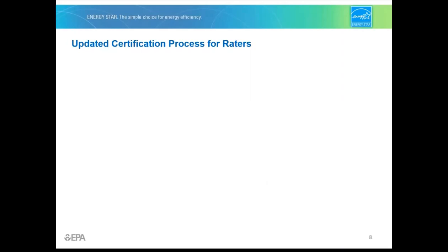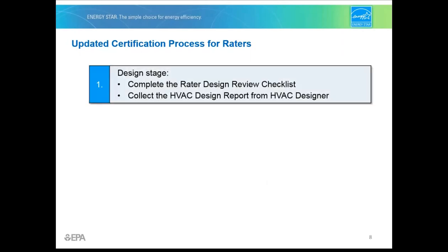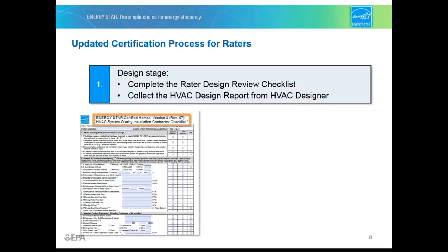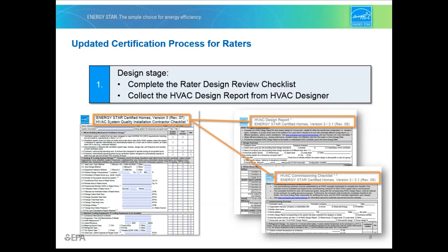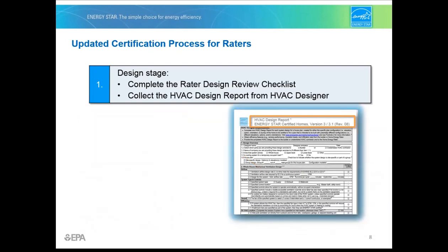Let's move on to the updated process for certifying a home and the role you'll play. At the design stage, you'll complete the rater design review checklist. Among other tasks, you'll review the HVAC design. With Revision 8, the HVAC system QI contractor checklist has also been split into two documents: the HVAC design report and the HVAC commissioning checklist. To review the HVAC design, you'll need to collect the HVAC design report — but this is the only design document you'll typically need. You'll no longer have to collect the full load calculations, the AHRI certificate, or separate documents for the ventilation design or air balancing.